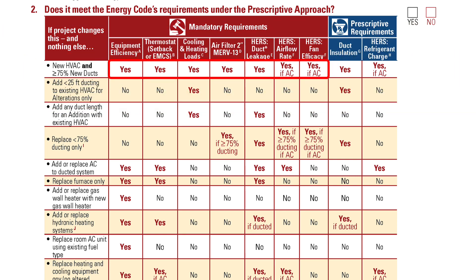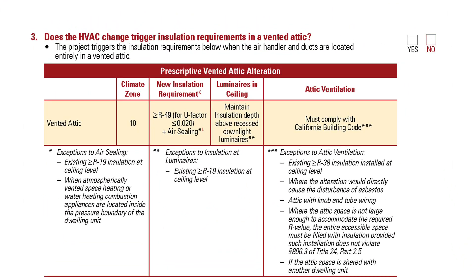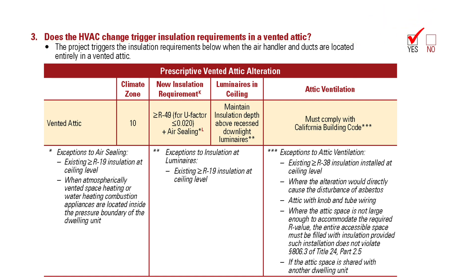When applicable, mandatory requirements can also appear in the checklist essentials page. In this case of a complete HVAC replacement, mandatory measures do apply. The next question is: does the HVAC change trigger insulation requirements in a vented attic? In this case, you determine the project is located entirely in a vented attic, so it does trigger insulation requirements.